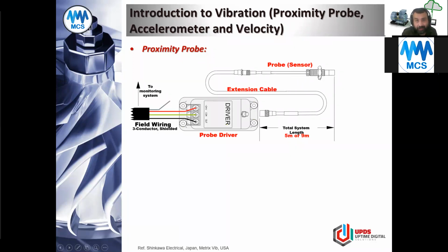This is what we call a sensing element. Later on, you have the extension cable, and later on the driver or the modulator or oscillator. From this point, the sensor is ended. Why are we saying the sensor is three pieces? Because you cannot manipulate any of these elements.